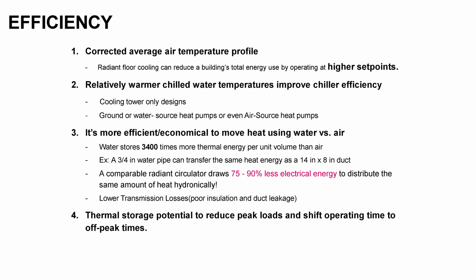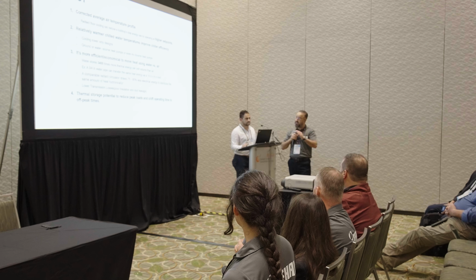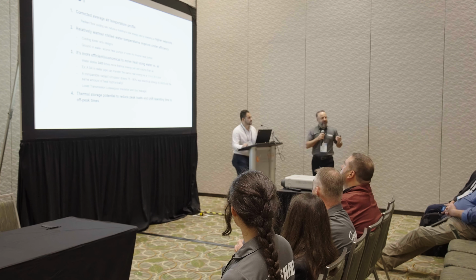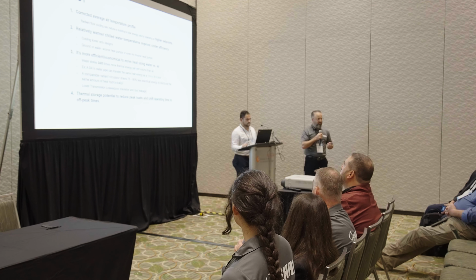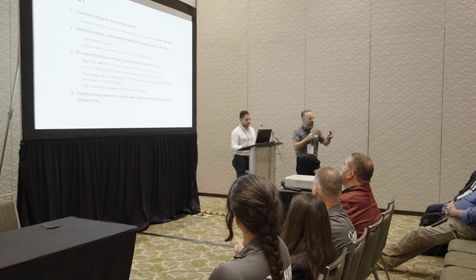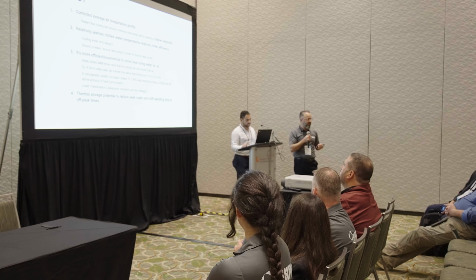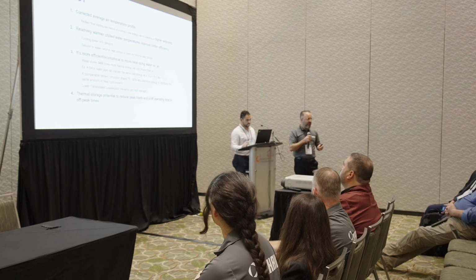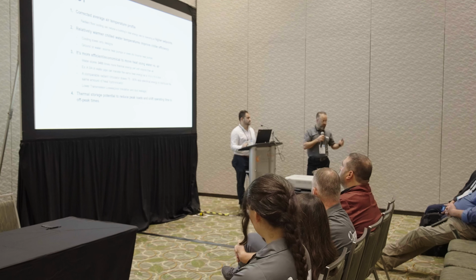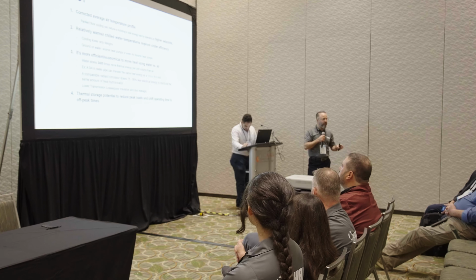But about efficiency, I was talking about the corrected thermal profile. That's one important thing, because when you are calculating your cooling load, you're not targeting a very, very chilled indoor air set point. That's why your delta T between inside and outside is not very big. So first of all, you're saving on your cooling load calculation. Second, you are dealing with a relatively warmer supply temperature. For radiant cooling, what we require in most cases is a 60 degrees Fahrenheit supply temperature, which is around 15 degrees Celsius. Whereas most of the, let's say, other HVAC systems may require way lower temperatures.